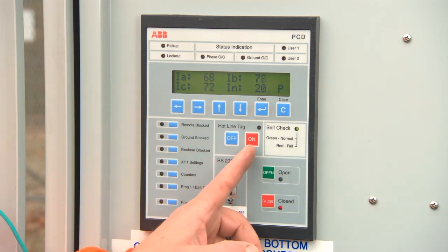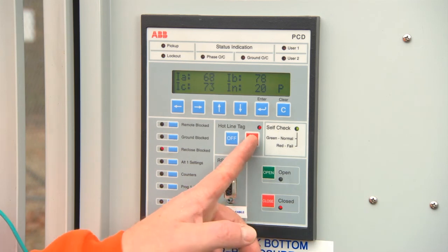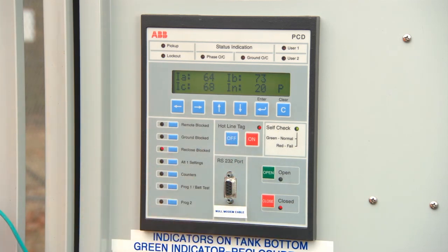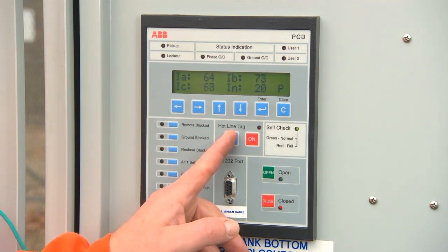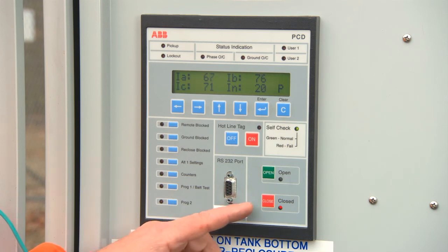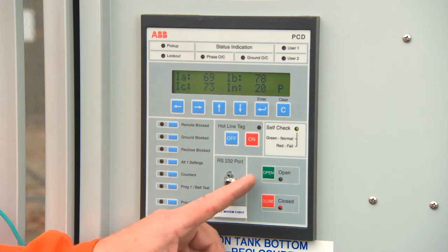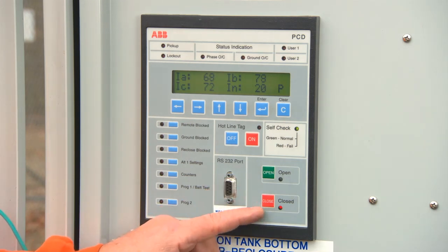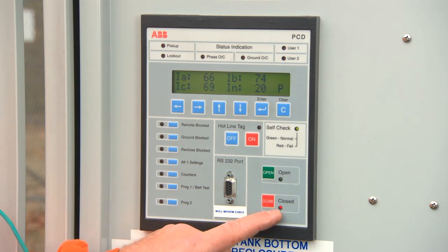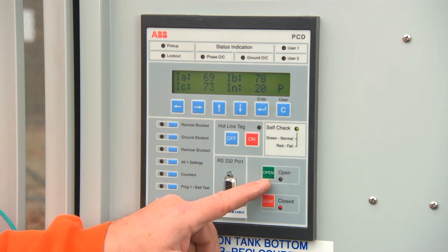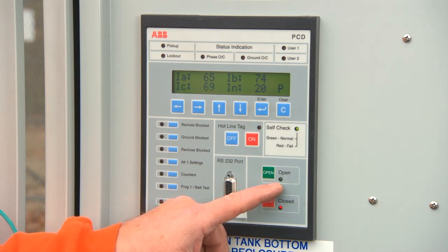Hotline tag. Pressing this red button will turn on the hotline tag. This will give you one shot until lockout. The indicator will turn red. Pressing the blue off button will turn it off. The indicator LED will turn off. Next are the red close and green trip buttons. When the unit is closed, the closed indicator will be red. Pressing the open button will activate its green LED indicator.